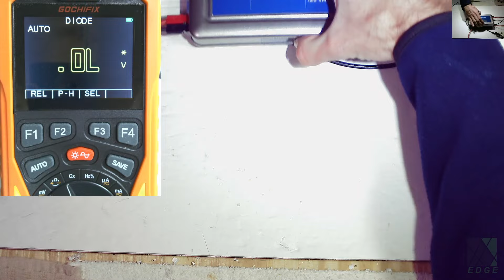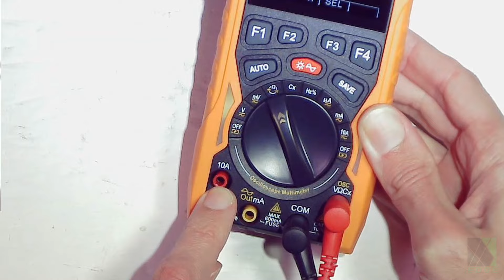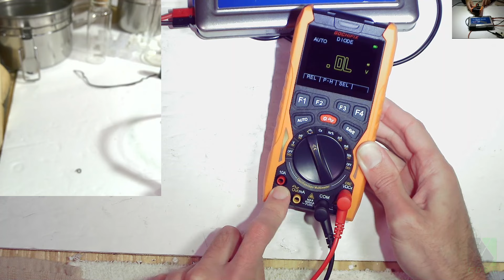The first thing you want to do is take the meter and put it over here. The first thing you want to do with any multimeter before you take a voltage measurement is make sure you're not plugged into the 10 amp range, which is right here, and make sure you're plugged into common and voltage, which I am. Because if you plug it in here and try to measure the AC outlet on an inverter or on the wall in a house, it will just blow the fuse and could damage the meter. But of course I'm not plugged into 10 amps, so I'm going to go ahead and make the measurement.